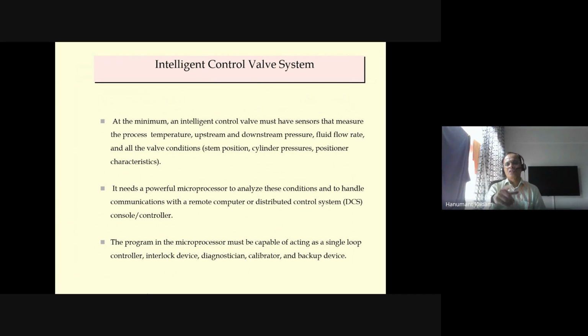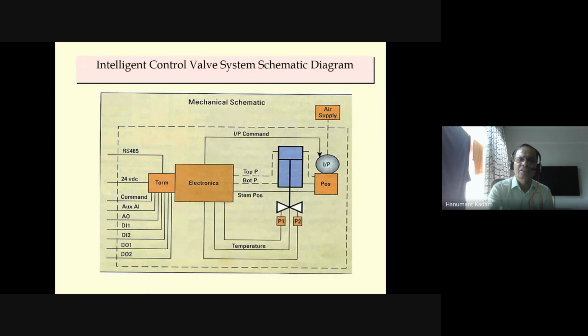So we are talking here about features of the intelligent control valve system. At the minimum, the intelligent control valve must have sensors that measure the process temperature, upstream and downstream pressure, fluid flow rate, and all the valve conditions, meaning stem position, cylinder pressure, and positioner characteristics. I have shown this in the block diagram. See these inputs. You can again check this: temperature, pressure, stem position, and these are the cylinder pressures, meaning above and bottom.